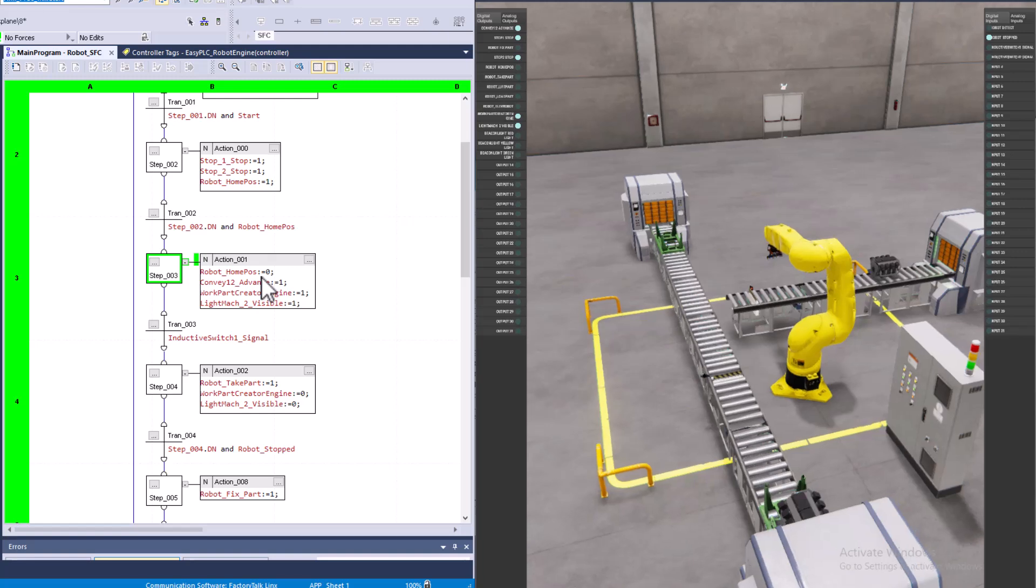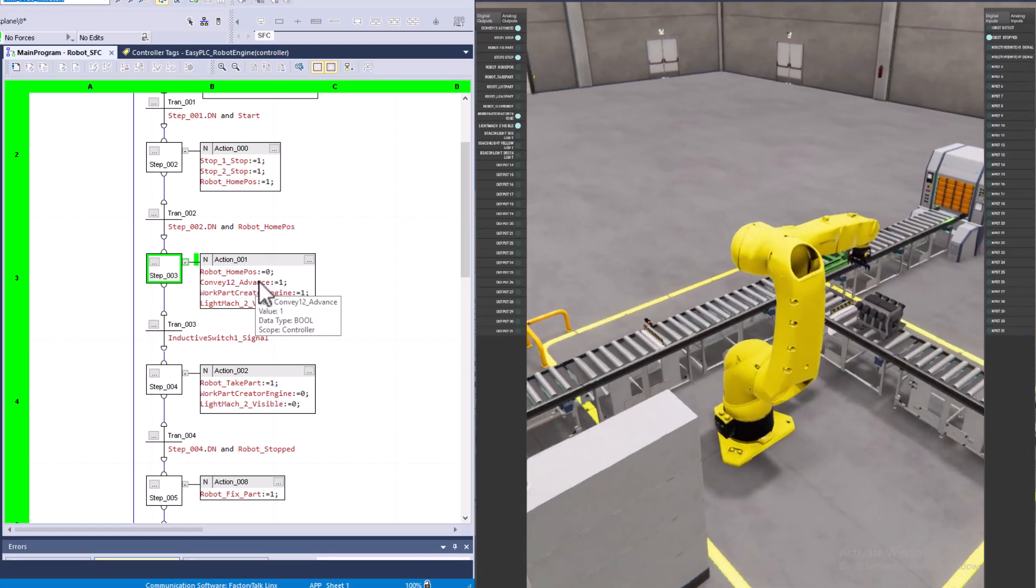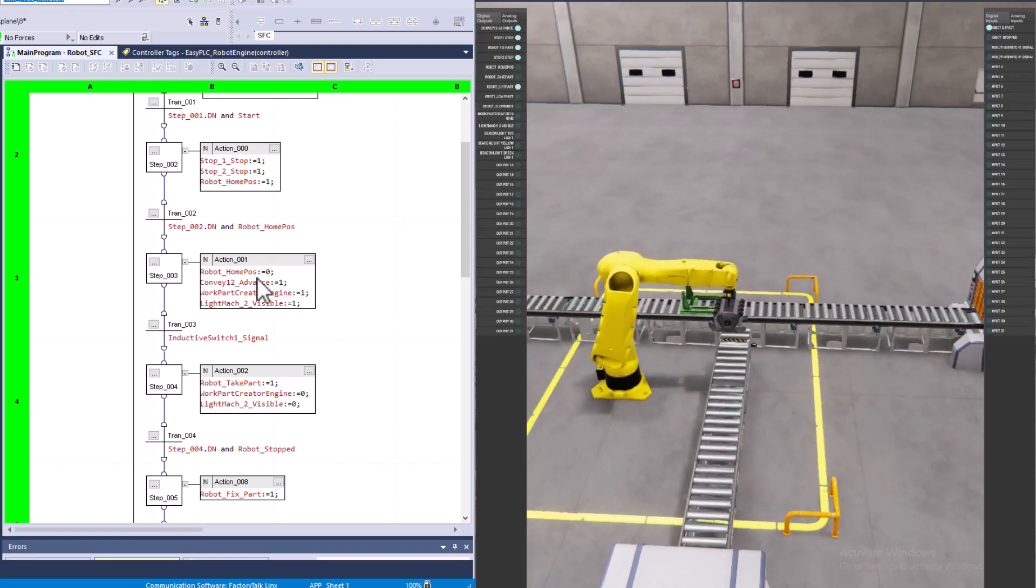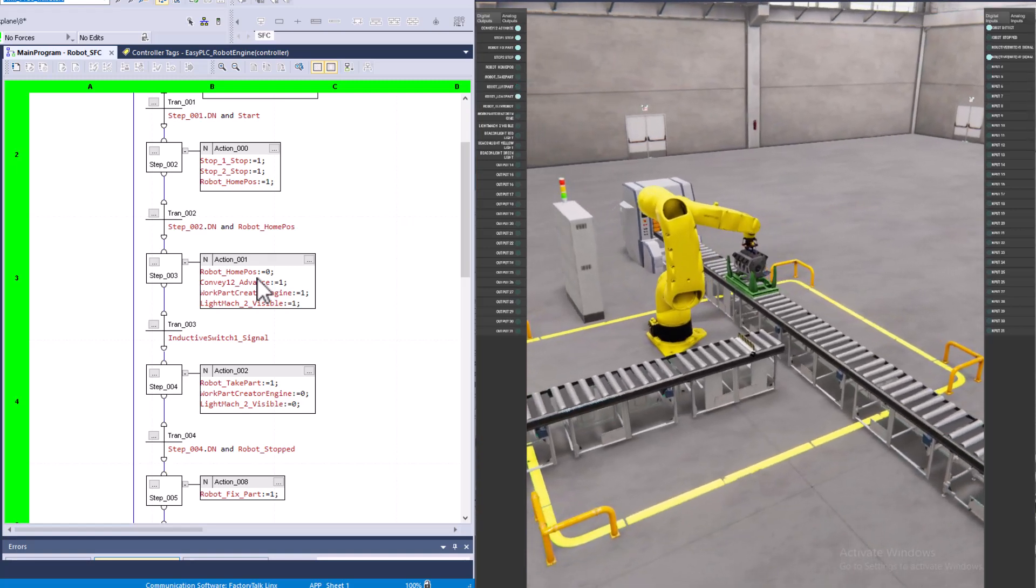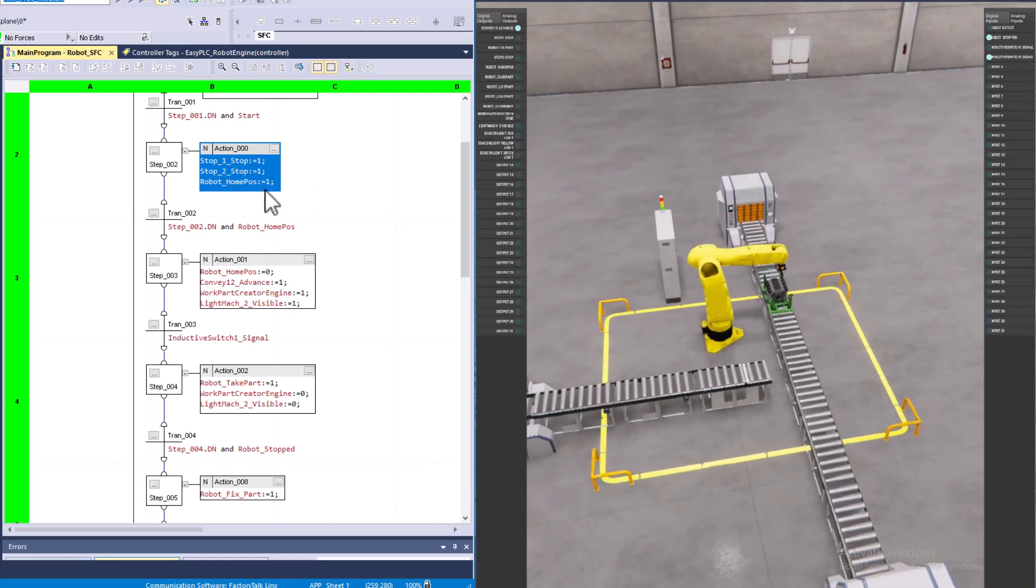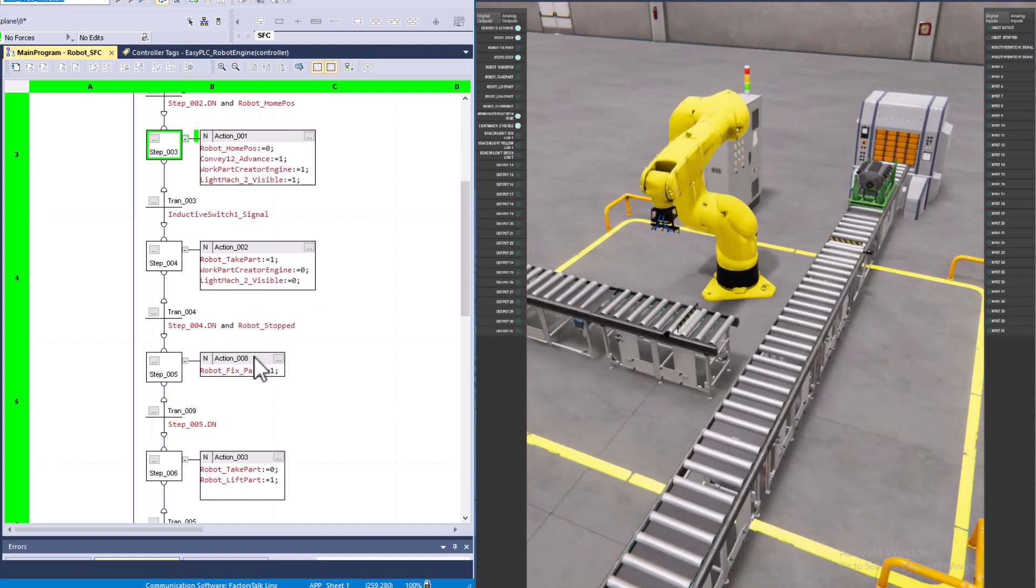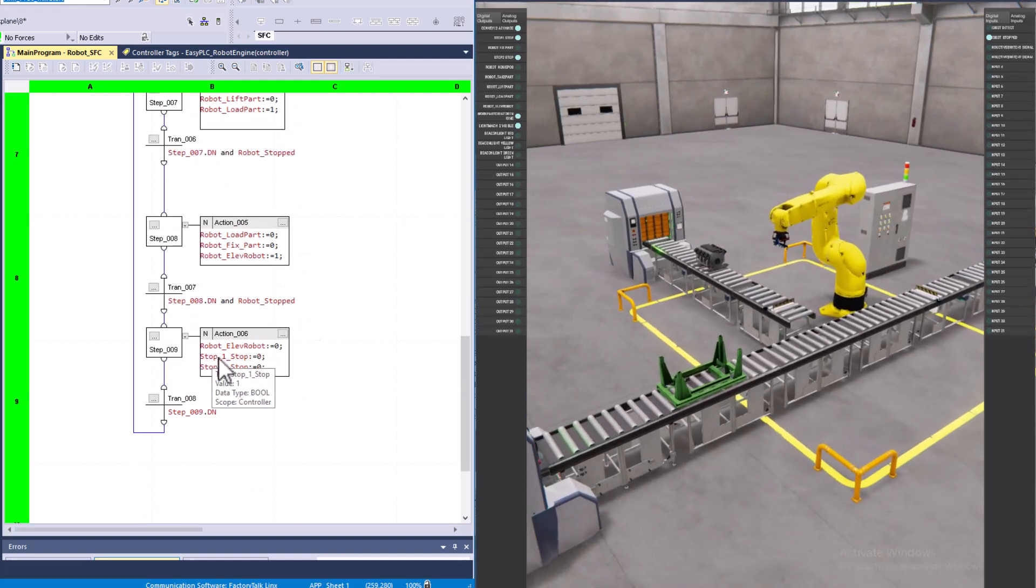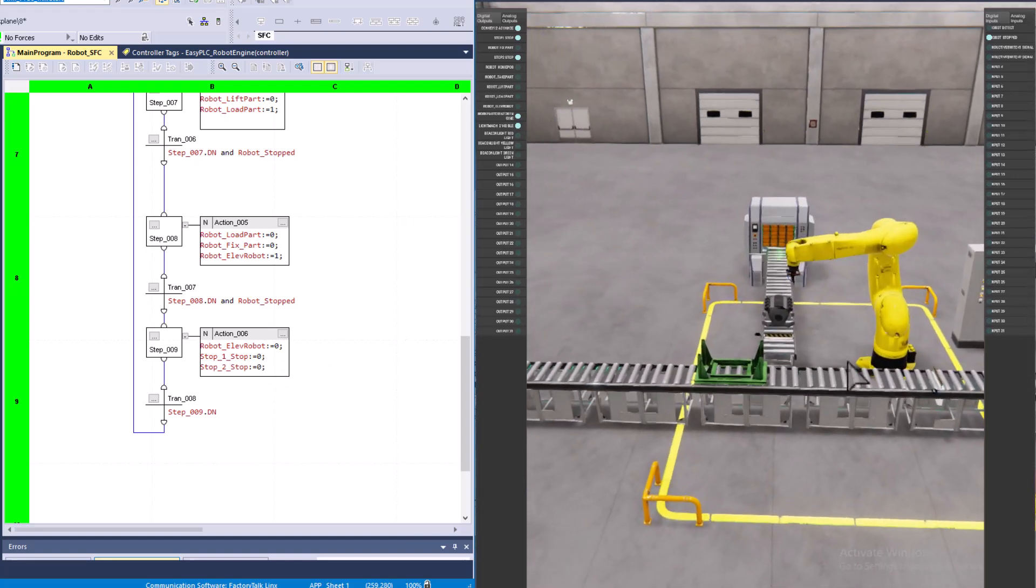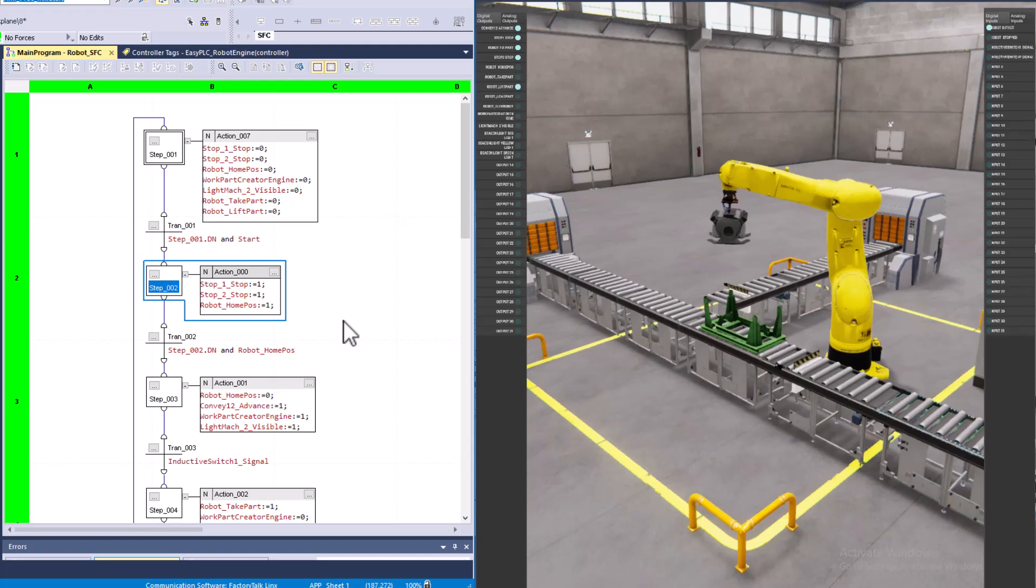I'm telling the robot, hey, go home. In sequential function chart you're using structured text. The way you write it, if you tell it to come on in one step, on another step you're going to have to tell it to come off. Like the stops right here, stops one and two, I tell them come on at the same time. I also tell the robot to go home, and later on I'll tell the stops to go down. You can see both stops when it hits the certain point, like step two right here.